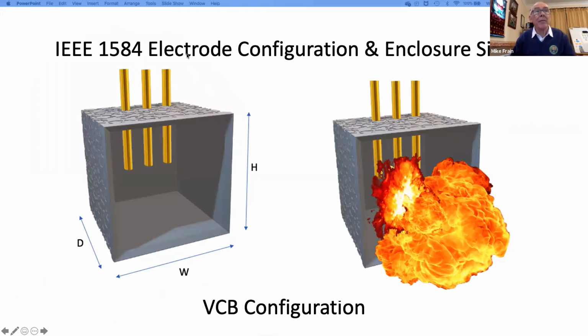So I talked earlier about the IEEE 1584 electrode configuration and enclosure sizes, and I've reproduced all of them here, to let you have a look at them and what they actually mean. The first one is what we call the VCB configuration, which is vertical conductors within a box, basically. And this actually appeared in the 2002 version, and it uses 3 equally spaced vertical conductors within the box itself. And actually what happens in practice is the arc is driven away from the source of supply and downwards to the bottom of the enclosure and arcs out.